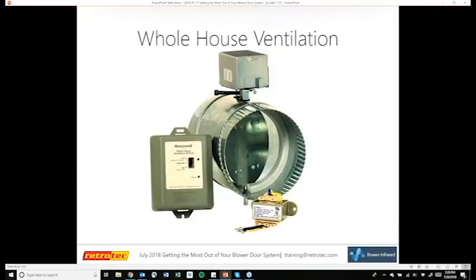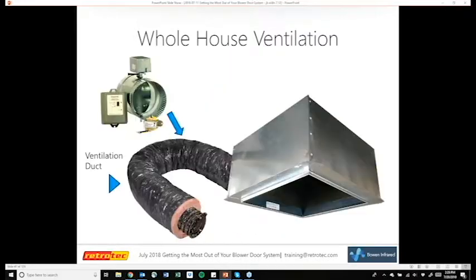So this is the one that Honeywell makes. This is just an example. There's several different ones out there. Aprilaire makes one. AirCycler is another brand that makes one. But basically what this does is that you have a ventilation duct that ties into the return side of the system. A lot of the times it's on the return box, so that way it can be filtered from the inside. Other times it'll be on the return trunk line or on the plenum and then be filtered from the outside. It is important that it is filtered somewhere and that the homeowner can get to it.